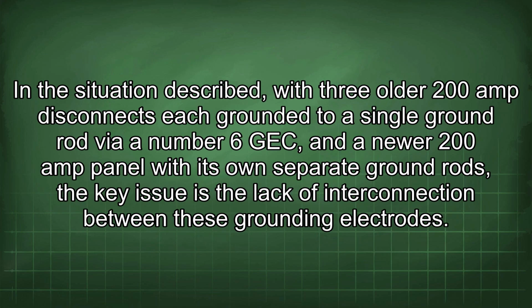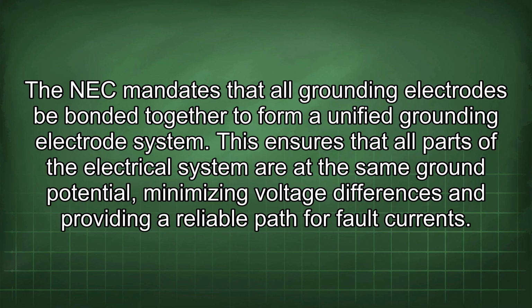In the situation described, with 3 older 200 amp disconnects each grounded to a single ground rod via number 6 GEC and a newer 200 amp panel with its own separate ground rods, the key issue is the lack of interconnection between these grounding electrodes. The NEC mandates that all grounding electrodes be bonded together to form a unified grounding electrode system. This ensures that all parts of the electrical system are at the same ground potential, minimizing voltage differences and providing a reliable path for fault currents.